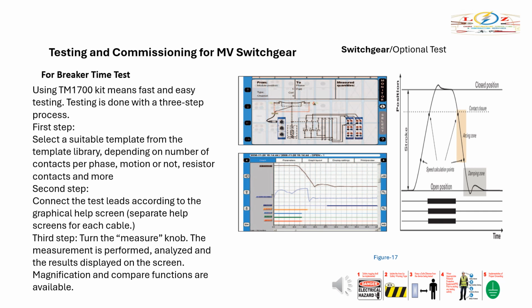Simultaneous measurements within a single phase are important in situations where a number of contacts are connected in series. The breaker becomes a voltage divider when it opens a circuit. If the time differences are too great, the voltage becomes too high across one contact, and the tolerance for most types of breakers is less than 2 milliseconds. The time tolerance for simultaneous measurements between phases is greater for a 3-phase power transmission system running at 50 Hz, since there is always 3.33 milliseconds between zero crossovers. Even so, the time tolerance is usually specified as less than 2 milliseconds for such systems.